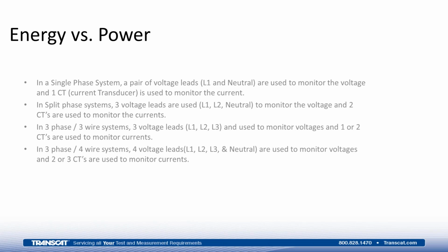The split-phase system would be used primarily, again, for residential and small commercial facilities. In this case, we would need 3 voltage leads because there are 2 active conductors bringing voltage into your facilities. We refer to those as L1 and L2, and they're both related to the neutral wire, which comes in also. So to properly monitor that, we would need 3 wires: 1 connected to L1, 1 connected to L2, and a 3rd connected to the neutral, which now allows us to monitor both of those voltages.